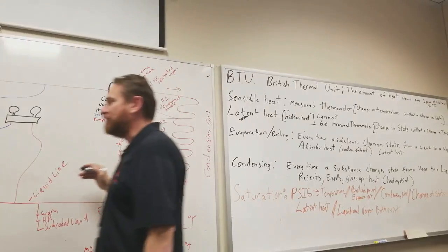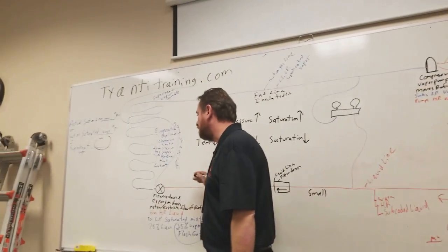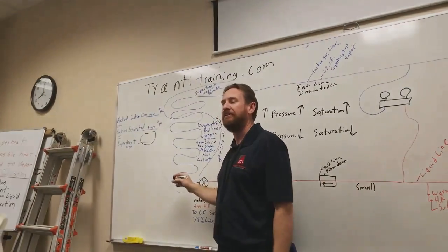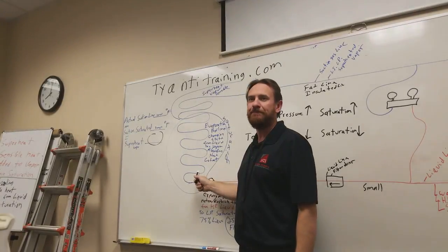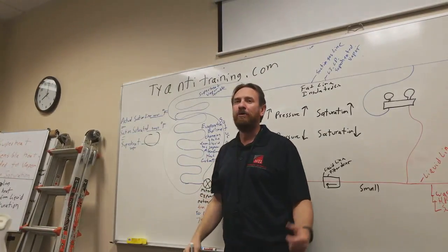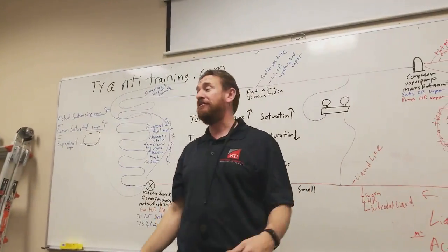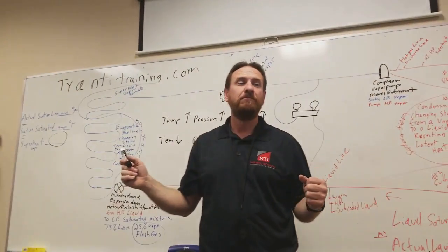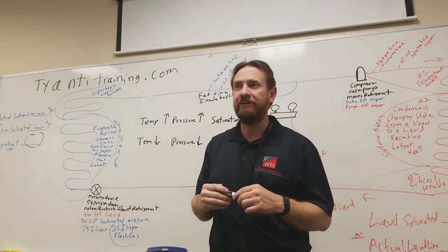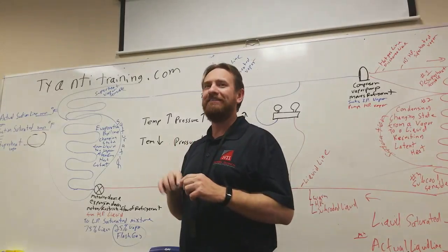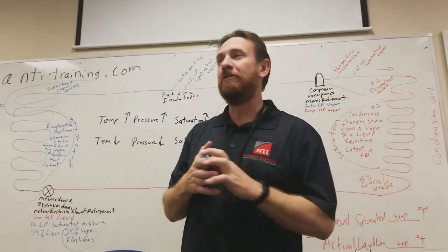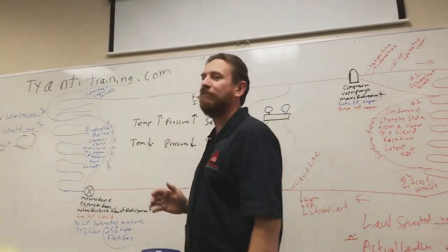So if I have higher pressure here, that means there's more pressure and more refrigerant, more molecules coming through this metering device. So what's going to happen to my pressure over here? It's going to go up. So will being overcharged cause the saturated temperature to be below 32? No. So being overcharged, will it cause it to freeze? No. But it is an issue because some people think only that it's low in refrigerant.